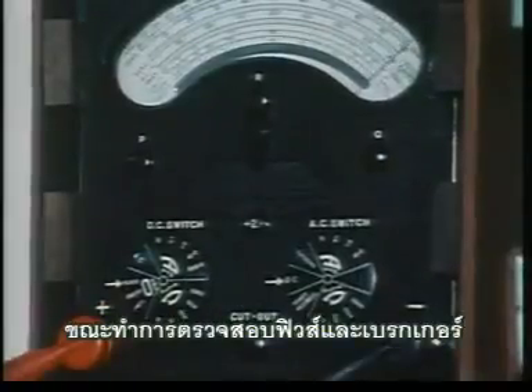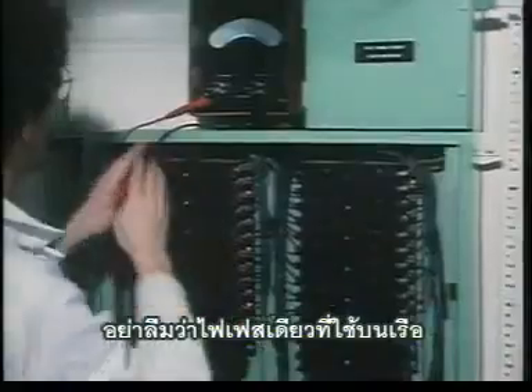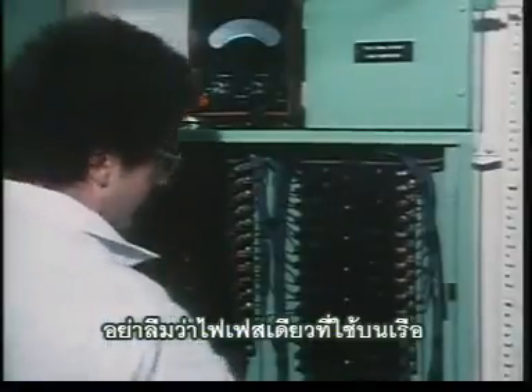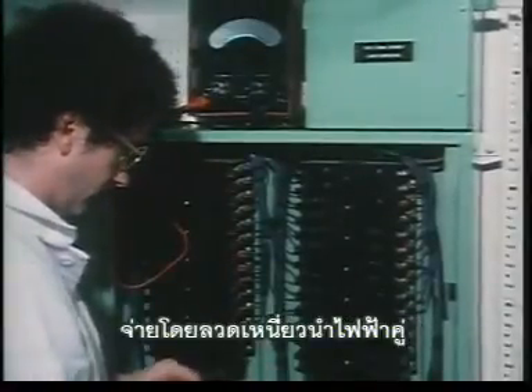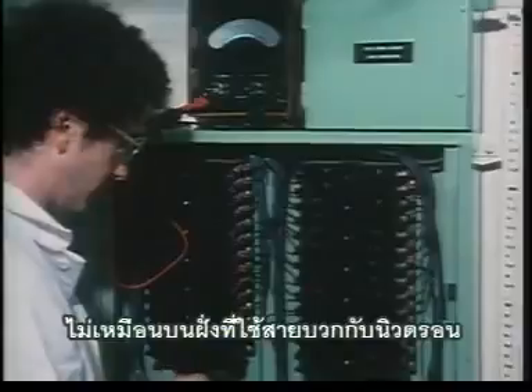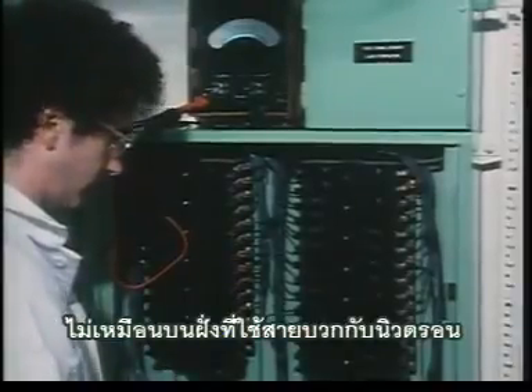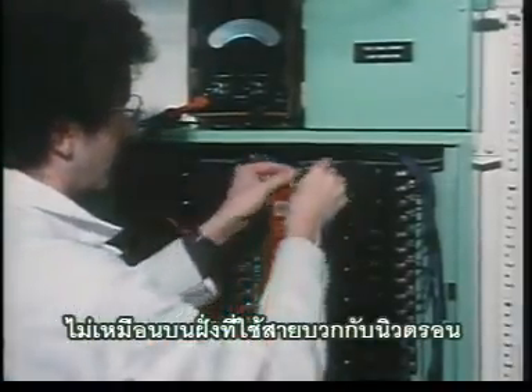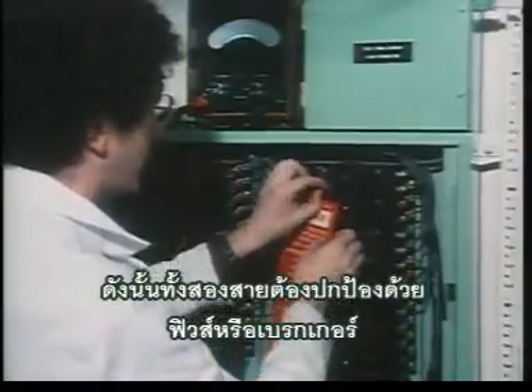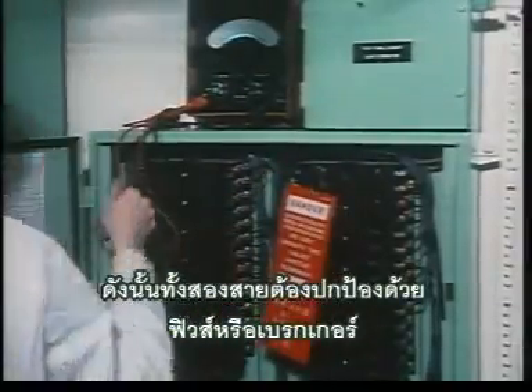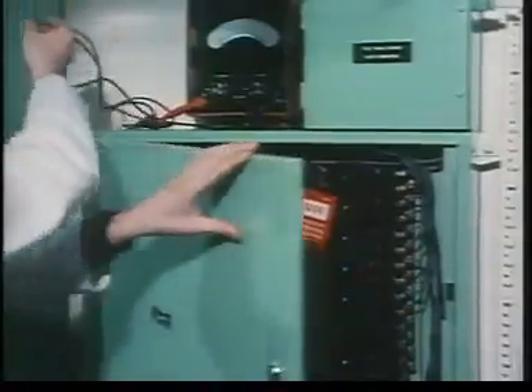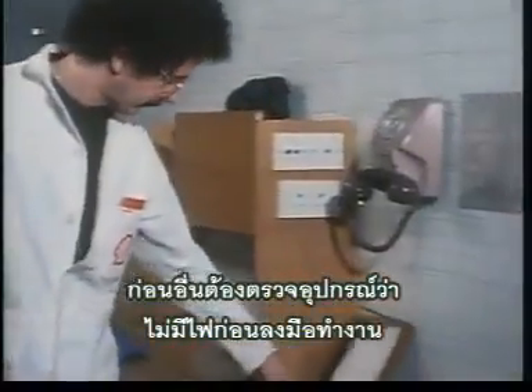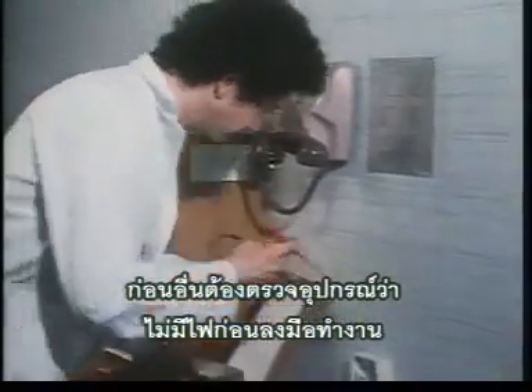While investigating fuses and circuit breakers, it's important to remember that a single-phase supply on board ship is distributed on 2 live conductors and not, as on shore, by a live and a neutral conductor. Therefore, both conductors must be protected by fuses or breakers. First, check that the appliance is dead before working on it.